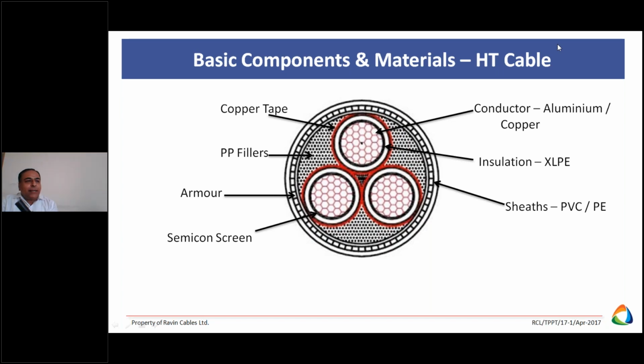You see, this is the insulated conductor we have removed from here. Here is the conductor, then conductor screen, then insulation, and overall black color. Similarly, you can see here conductor screen, the white patch is the insulation, then black color is the semiconducting layer, red color is the copper tape. Then fillers are there. Then inner sheath, armoring, outer sheath. So these are the basic components normally used for the manufacture of the cable, right?